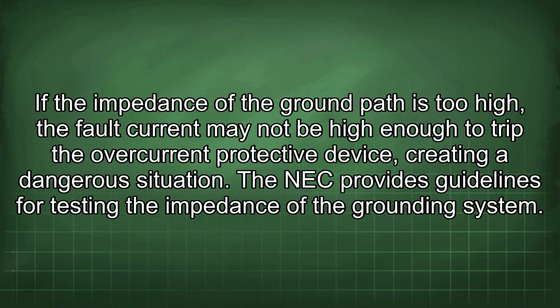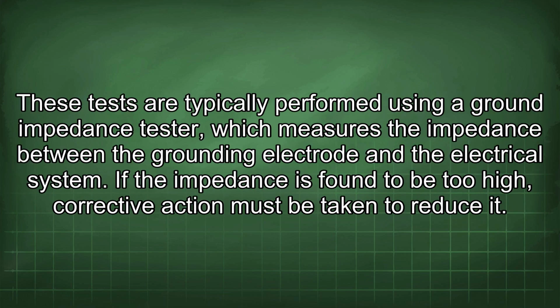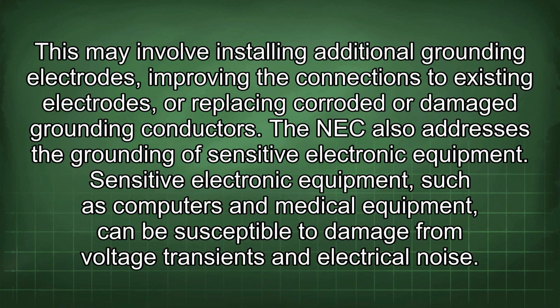The NEC provides guidelines for testing the impedance of the grounding system. These tests are typically performed using a ground impedance tester, which measures the impedance between the grounding electrode and the electrical system. If the impedance is found to be too high, corrective action must be taken to reduce it. This may involve installing additional grounding electrodes, improving the connections to existing electrodes, or replacing corroded or damaged grounding conductors.